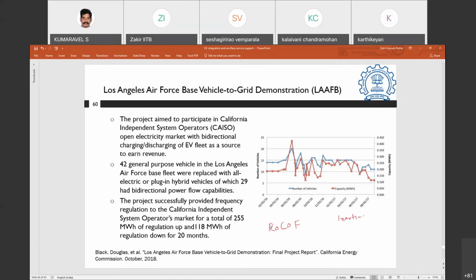So this ROCOF, rate of change of frequency, is dependent on what I was talking about, the inertia in the system. This swing equation is valid for synchronous machines, but even without that, this ROCOF, df by dt, is dependent on how much inertia is in the system. If you have higher inertia in the system, you will have a lower ROCOF.